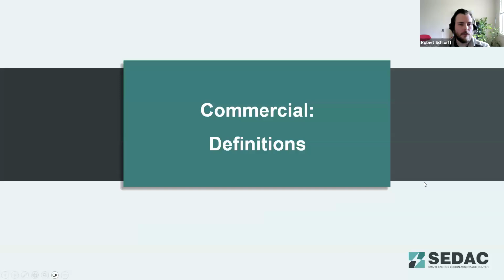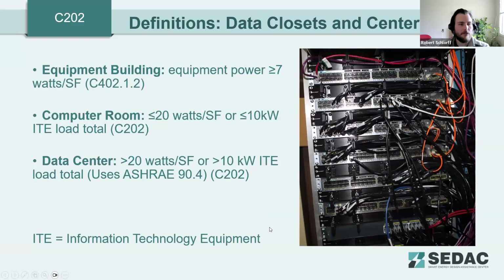All right, so let's start with a few quick commercial definition changes here. In the 2021 code, they have some new or updated definitions regarding IT equipment, data closets, and data centers. These are broken out as equipment buildings, where there is equipment power that is greater than or equal to 7 watts per square feet. And we'll talk a little bit more about those in a few slides. Computer rooms are defined as rooms that have equipment with less than or equal to 20 watts per square feet or less than or equal to 10 kilowatts of ITE load total. And ITE at the bottom of the slide there is information technology equipment.